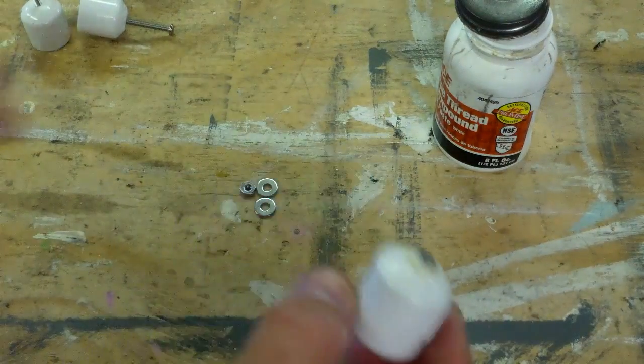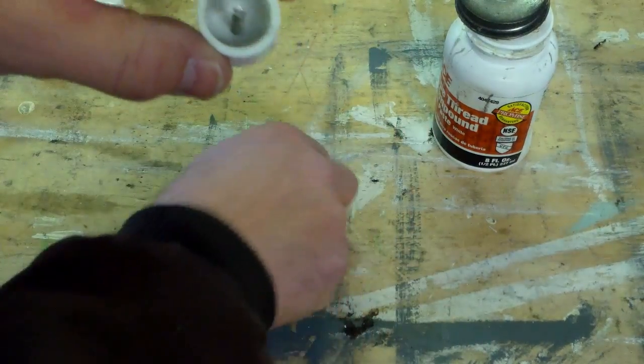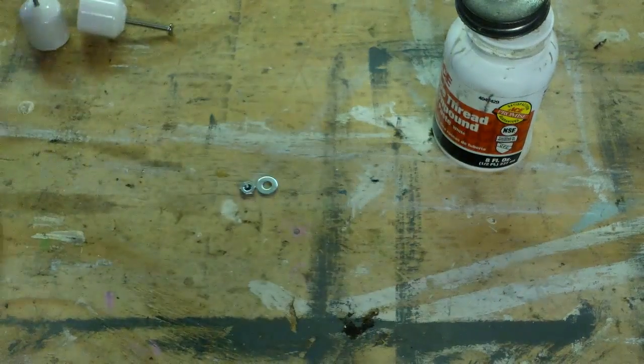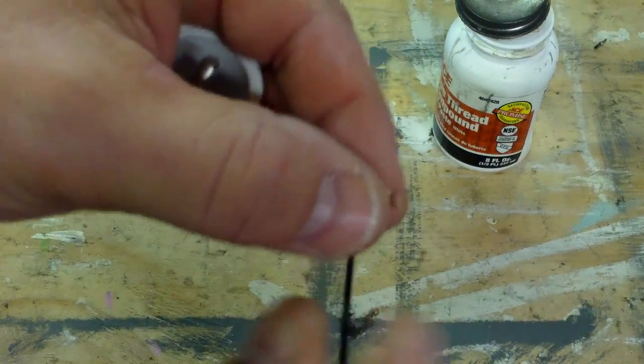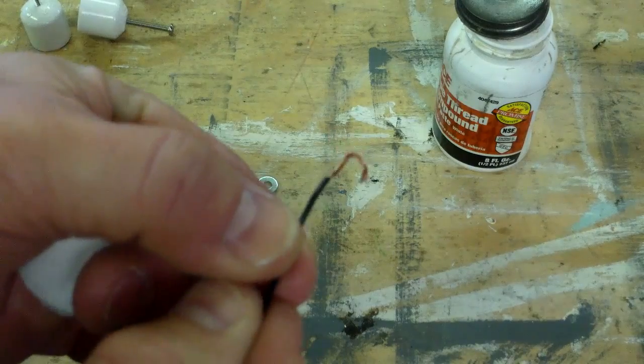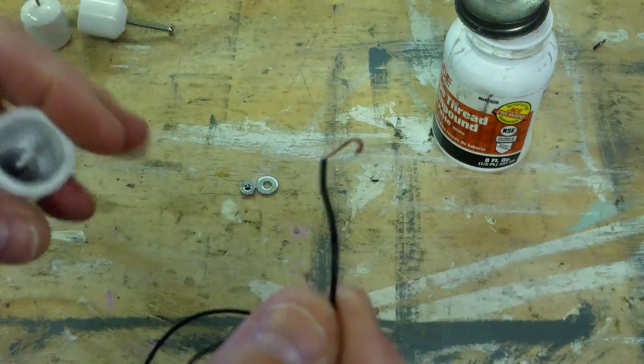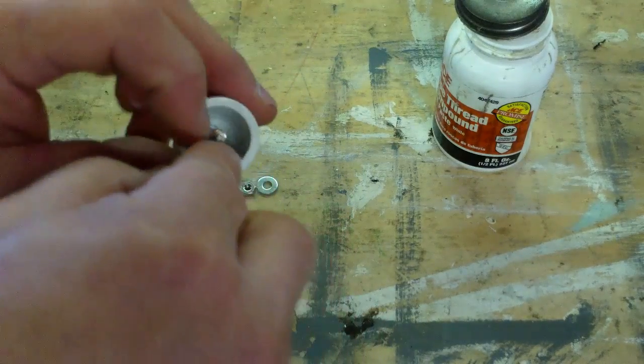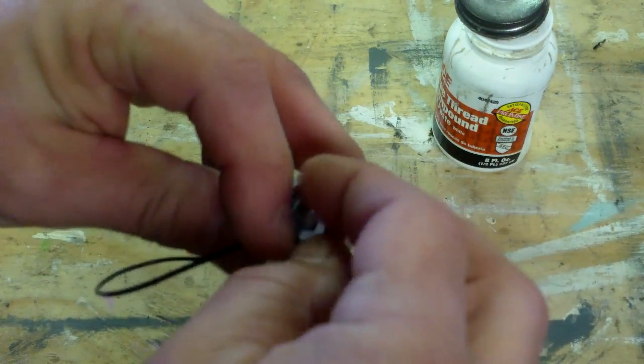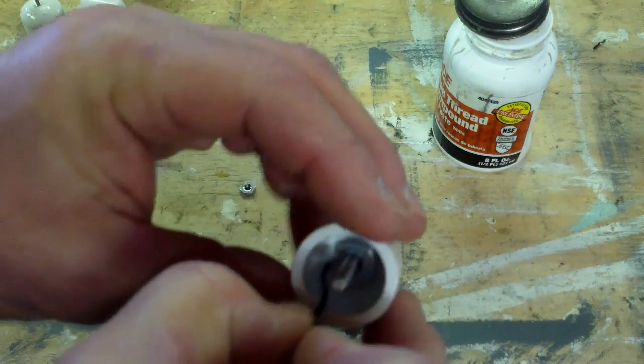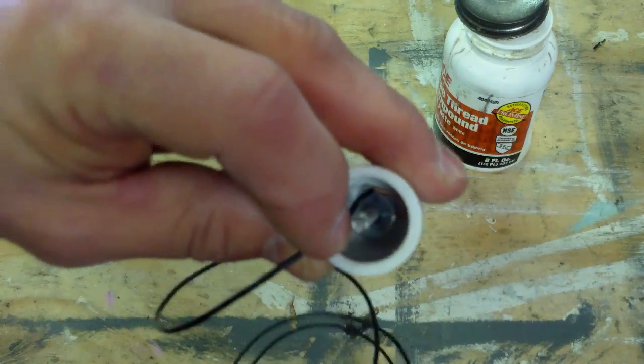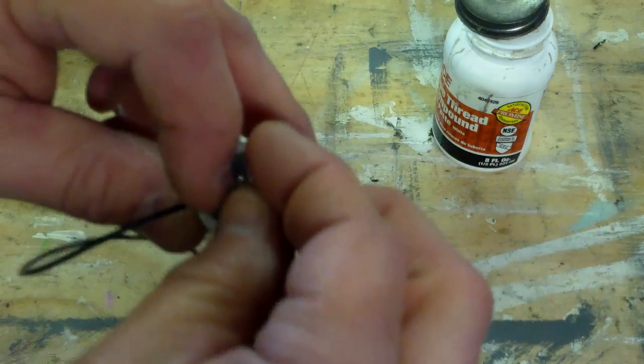Okay, the next thing you're going to want to do is just take your rag and get rid of some of this extra pipe compound where you've just got a little bead just going all the way around the screw. But we want the top of our screw clean because that's what's going to make the contact with the water. Now, once you've done that, you'll want to take one of your washers and just drop it on down in there, then take your section of wire with a loop in it like this, and then bend it at a 90 degree angle, drop it down in here. Then take another washer and just put it all, let it go all the way down in there like that. So what that's going to do is give us a pressure point that it's going to squeeze that wire and it's going to hold it in place.